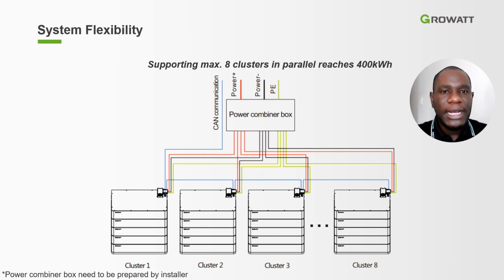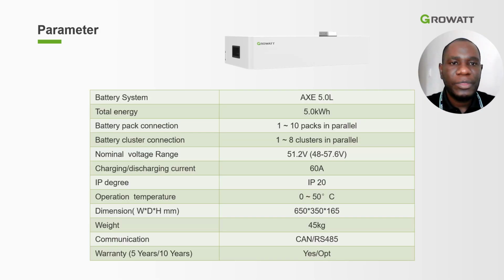Then if you want to have clusters that are more than 2, 3, 4, going all the way up to 8, then together with the use of a DC combiner box, you have only 2 power cables out of your combiner boxes, your positive and negative, and of course your earth going to your inverter, and your comms cable as well from one of the clusters all the way direct to the inverter.